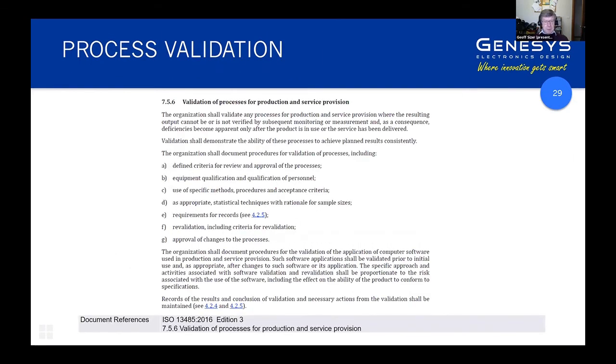So just to talk very briefly about process validation, this covers processes, for example, things that go on in biology laboratories and so forth. But in the case of an active MedTech device, it generally refers to the manufacturing process. So you're validating the process of manufacturing the device, but you'll notice it does have the service provision component down the bottom. Once again, the service provision aspect is kind of outside the scope to a degree of what this community is focusing on, but it is a very important part of the whole medical scene. But we tend to focus on active medical devices, where the main validation process is the manufacturing.